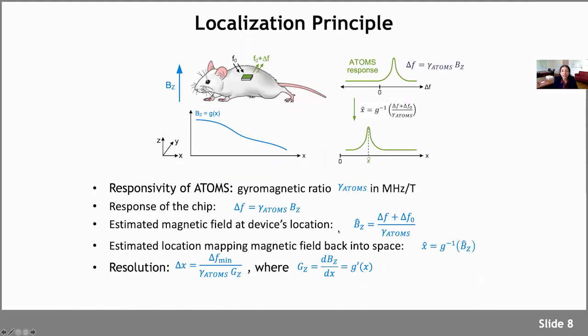So as you can imagine, the principle is actually quite simple. We have to generate a monotonic, well-known magnetic field with a known gradient. And then our chips will translate the measured magnetic field to a delta F with this factor of gamma. And then we have to look at the profile of the magnetic field and look at the inverse of that function to map it into location.